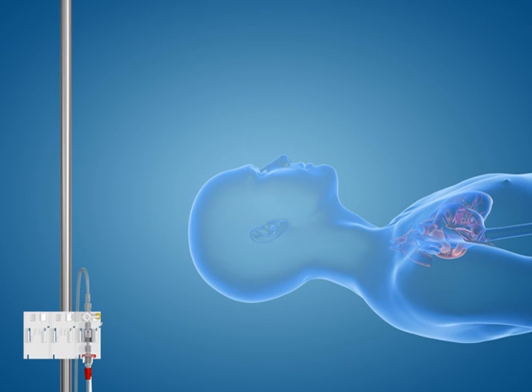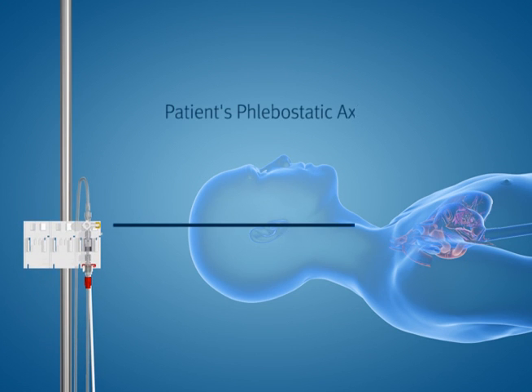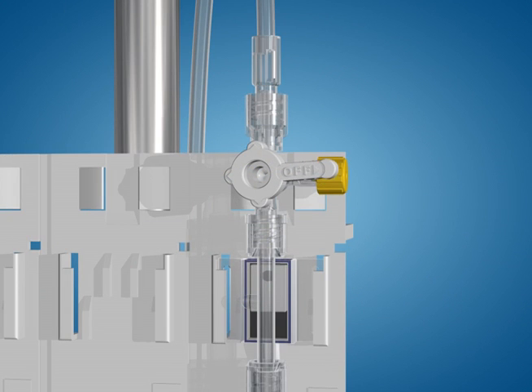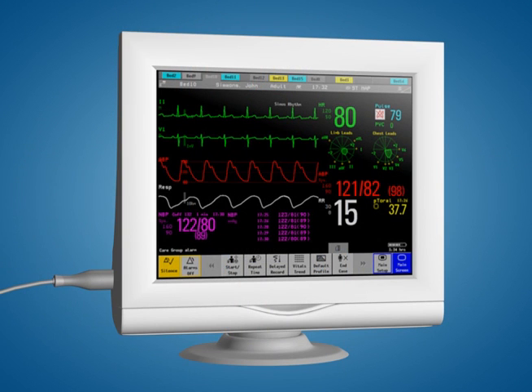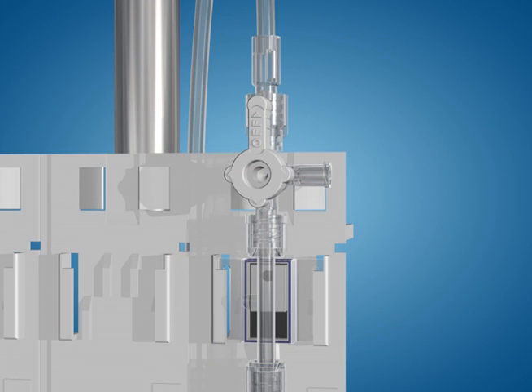Position the pole mount so that the zeroing stopcock port is level with the pressure source, the patient's phlebostatic axis. Turn the handle of the zeroing stopcock off towards the patient line. Remove the yellow non-vented cap from the zeroing port, which opens the transducer to atmosphere. Zero balance and calibrate the monitor according to the manufacturer's instructions. When completed, turn the zeroing stopcock handle off towards the zeroing port, and replace the yellow non-vented cap on the zeroing port.